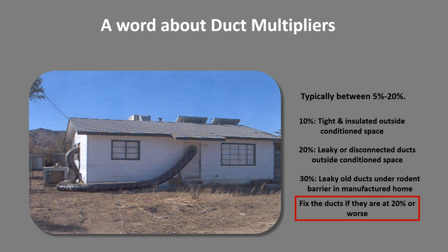Duct multipliers typically range from 10 to 30%. If the ducts are inside the house, 0 is a good number, but boy, if they're in attic and crawl spaces. But as good as you can do is a very tight duct system with at least R8 insulation. 20% starts to go up there. And honestly, if you're using 30% duct multipliers or 40% duct multipliers, you really should fix the ducts before moving on.